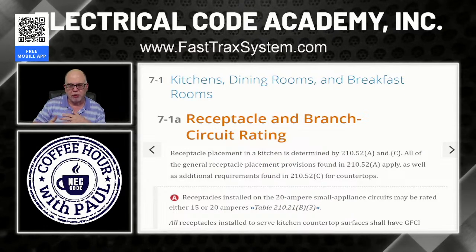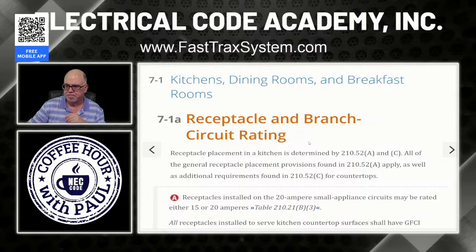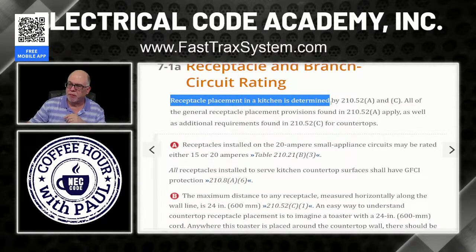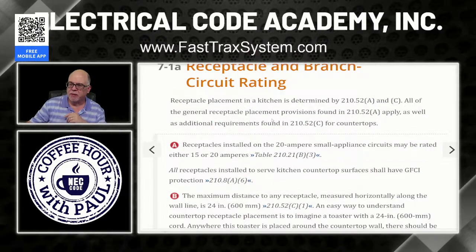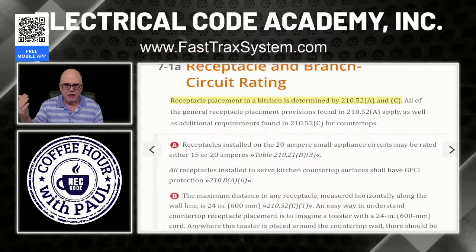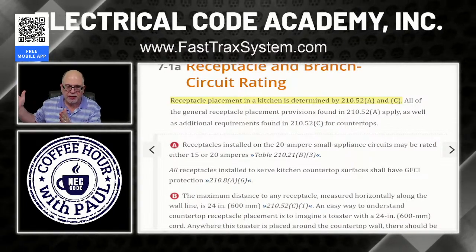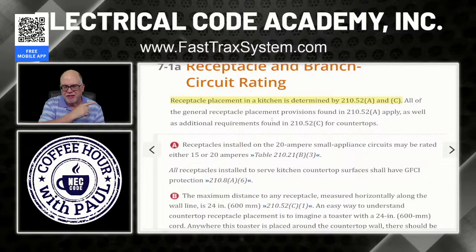And this is just building onto a previous episode, where we talked about normal receptacle placements and spacing and things like that. All right, let's get into it here. Receptacle placement in a kitchen is determined by 210.52A and C. So let me clarify this. In a previous episode, we talked about 210.52A. That's the 6-foot, 12-foot rule, right? Going around the room, a break in the floor line along the wall is where you start your measurements. Go 6 feet from that break, and then you could go a maximum of 12 feet to the next receptacle.